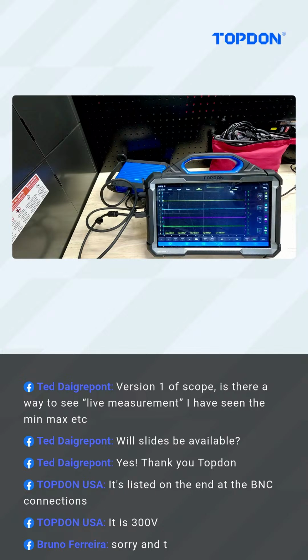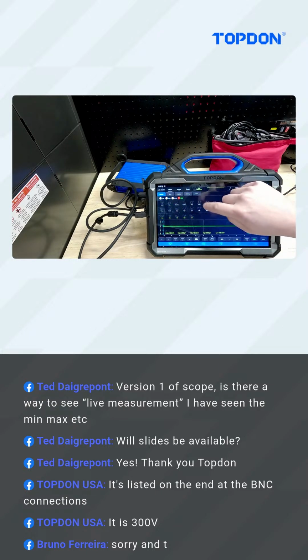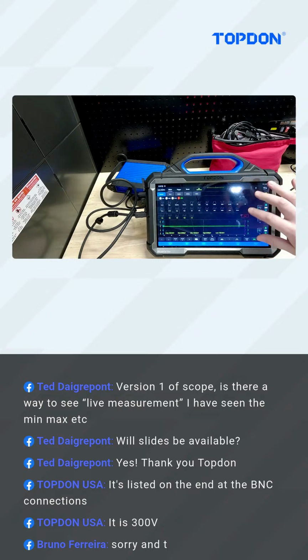Okay, so as we're looking at this, we have the ability to go to the menu. We can go into the measurement section here. And when we're in the measurement section, what we can physically see here is we can change each of the channels and then assign different measurements to each channel. And there's a pretty good list of measurements that we can use here, right? We can look at positive pulse width, like if we're looking at something that's duty cycled. We can measure the frequency, the period, amplitude, minimums, maximums, high, low, all of that stuff. RMS is typically used for something like an alternator AC voltage output to make sure we don't have excessive AC voltage. So again, there are all these different things, and you can measure each channel independently.